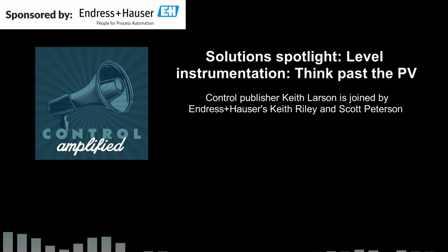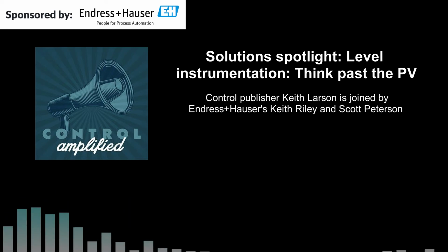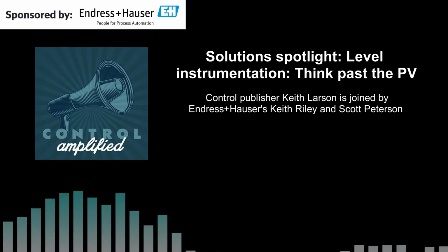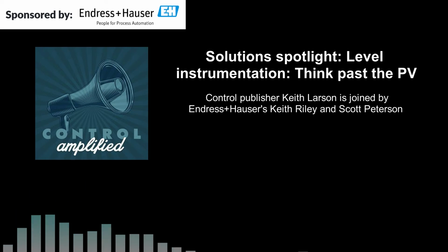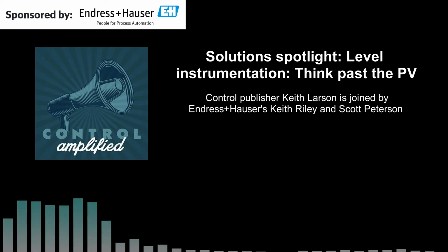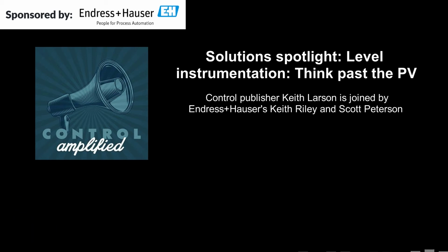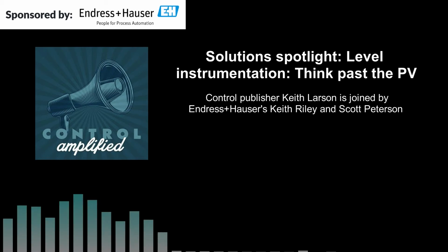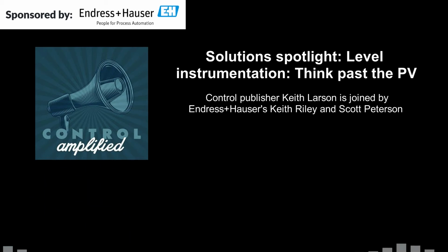The commissioning wizards that have come out as of late lend themselves to simplifying that setup process, eliminating the uncertainty, making it easy to set the necessary parameters. You have easy instrument-led directions. And as Keith mentioned earlier, Bluetooth is simplifying that process even further. Before Bluetooth, a typical service tech would have to locate a laptop or a handheld communicator, ensure the correct DTMs are loaded into the software, locate a modem that's the correct type to connect either at the device or out at a marshalling panel. With Bluetooth, a lot of that goes away. You really only need a cell phone to do your connection.